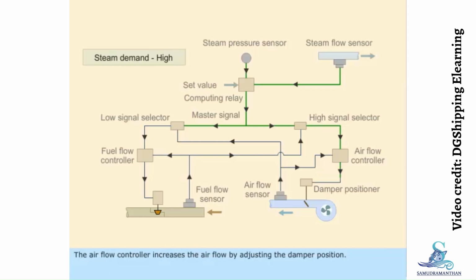The airflow controller increases the airflow by adjusting the damper position. As the airflow increases, the airflow sensor transmits the signal to the low signal selector and airflow controller. The master signal passes to the fuel flow controller to increase the flow of fuel by adjusting the fuel valve position.